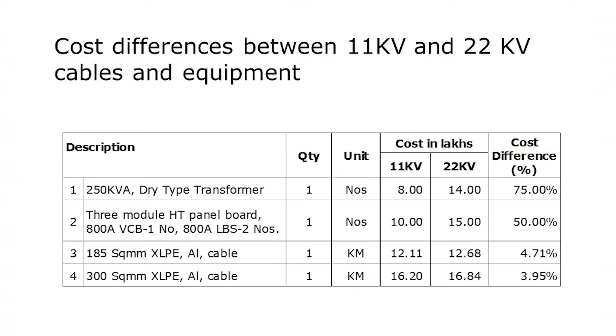So you can see why, also from a cost perspective, the migration to 11 kV is very interesting. Take a transformer, same 250 kVA: 11 kV would cost you 8 lakhs, 22 kV would cost you 14. Same thing for switchgear and cables. So there is a very strong case to go for 11 kilovolts.